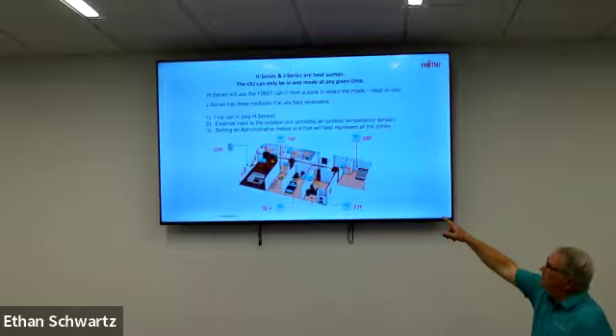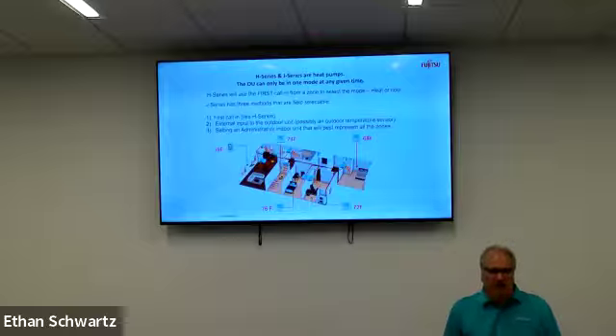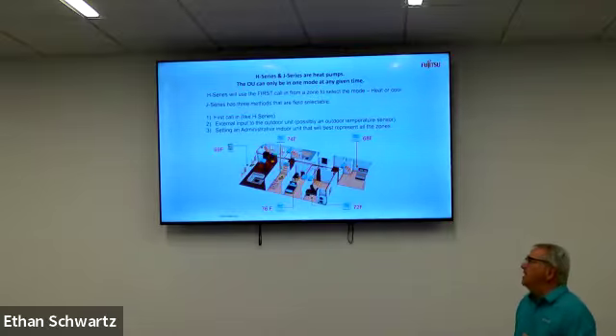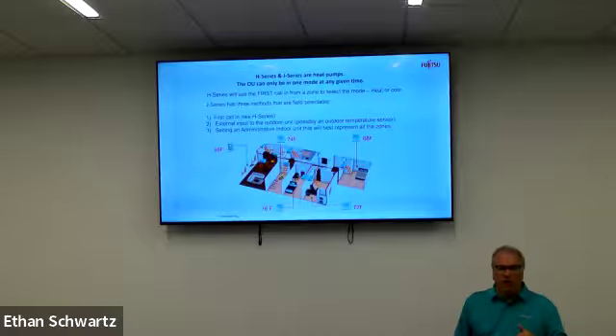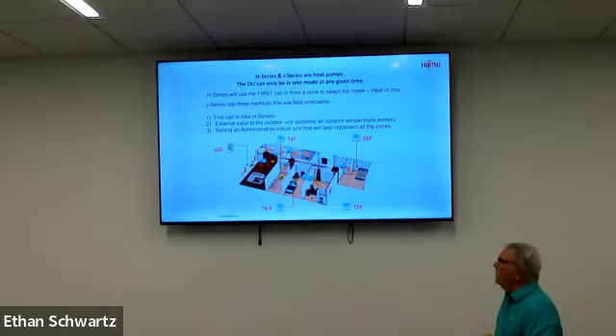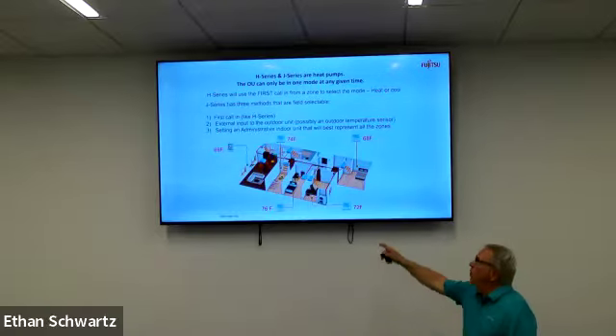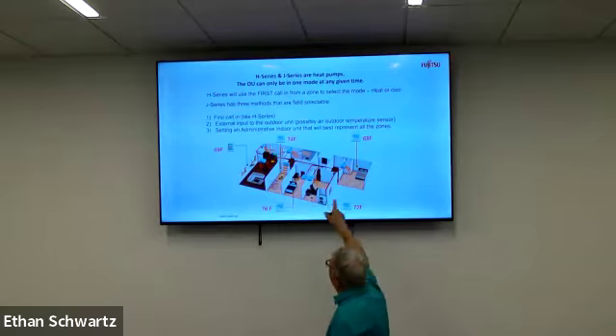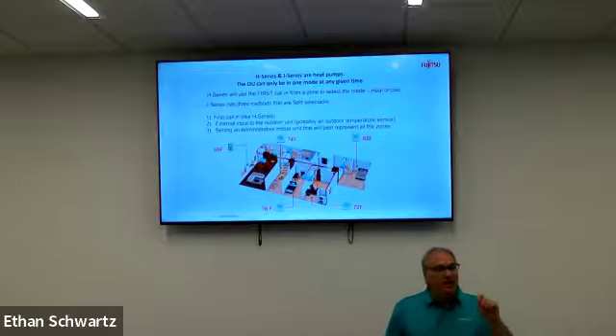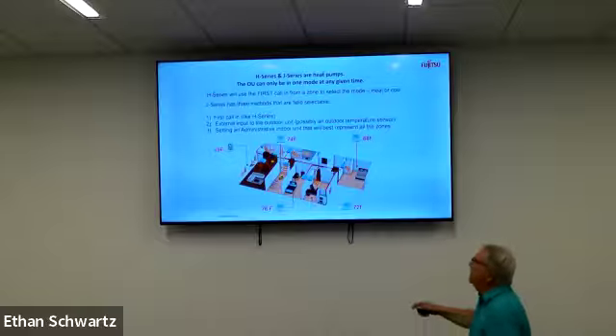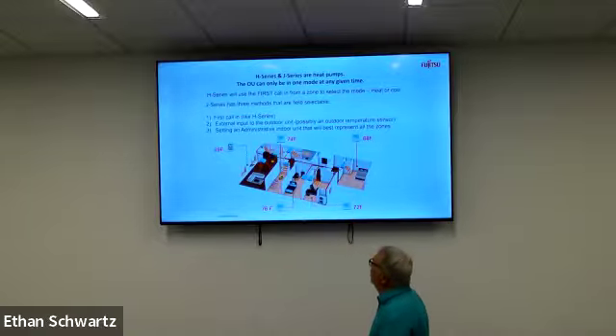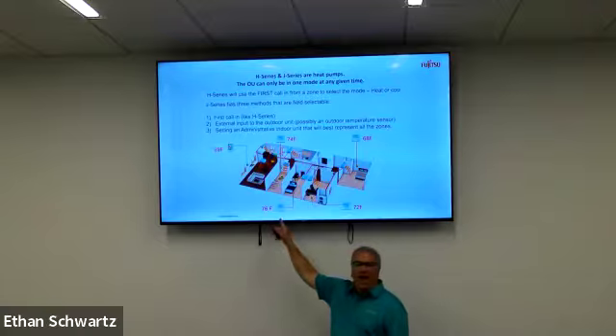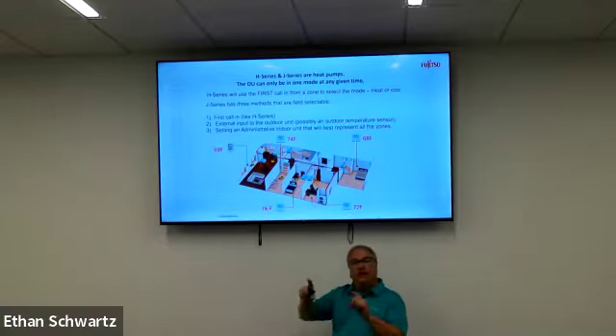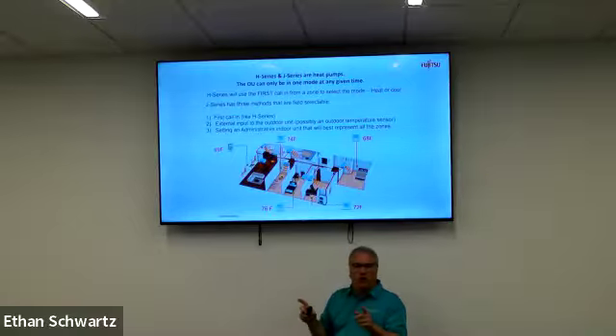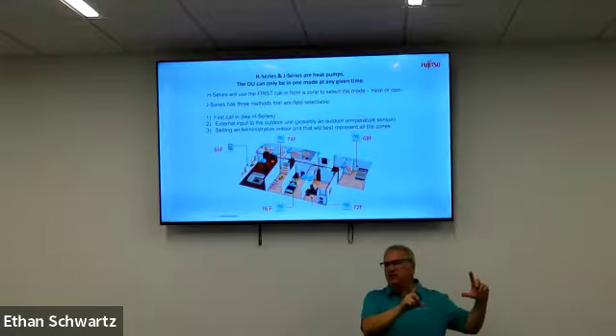And then the next thing is setting an administrative indoor unit. Very important. On every heat pump circuit, there will be an administrative indoor unit on the VRF side. And that says that of all of these controllers in this application, which one best represents the zone? Because then when you have an administrative indoor unit, the manager or occupant or owner can go to that administrative control and select what mode, kind of like what would be a centralized controller. So you wouldn't have to go to the full size of a centralized controller.